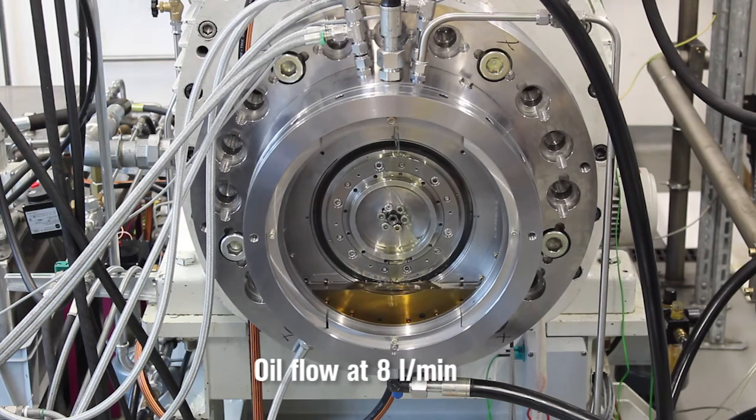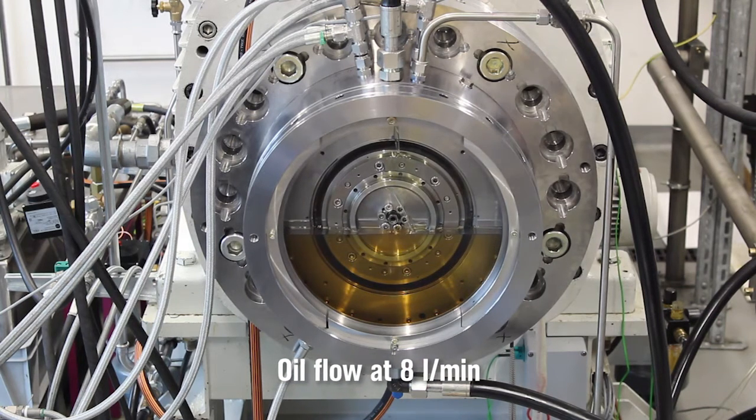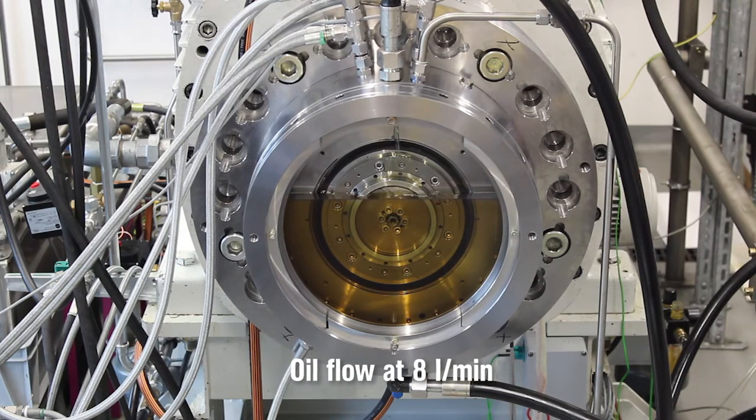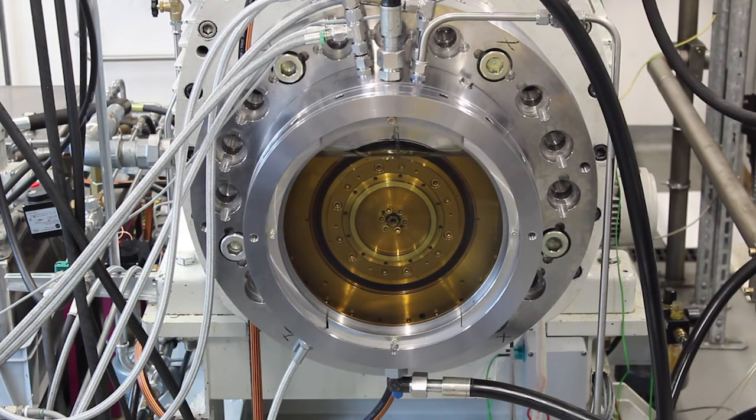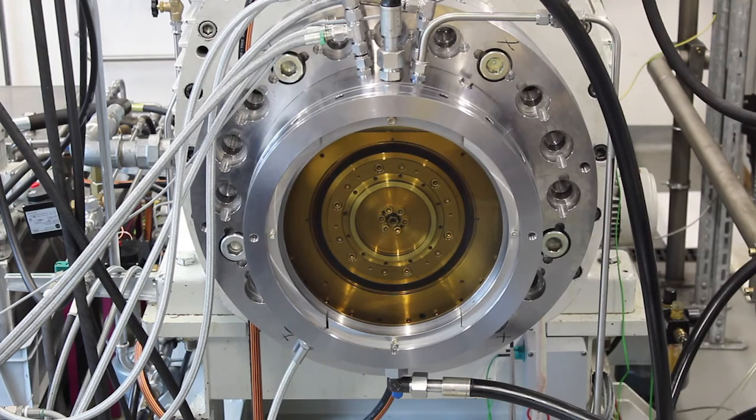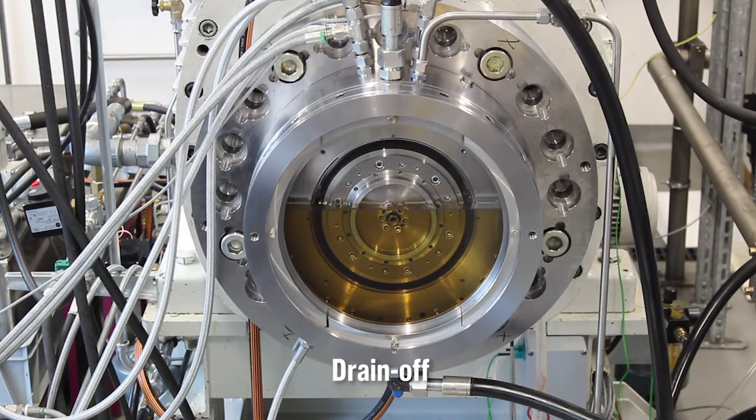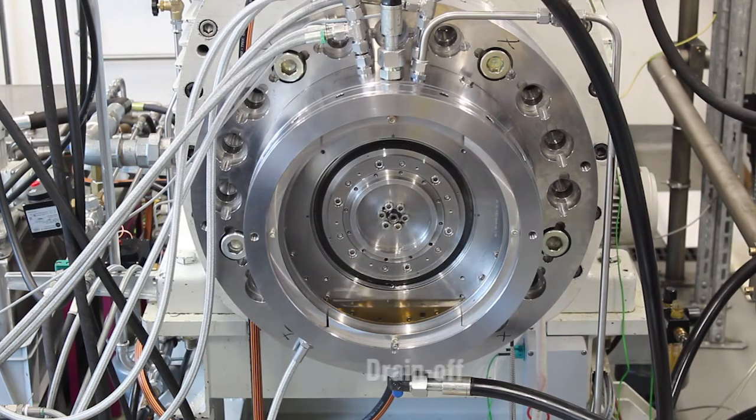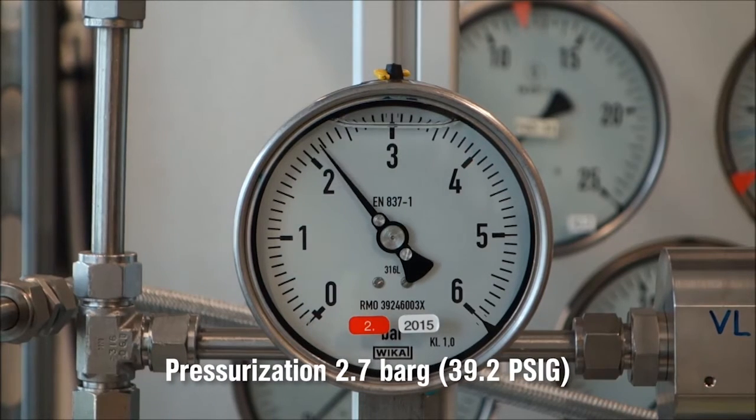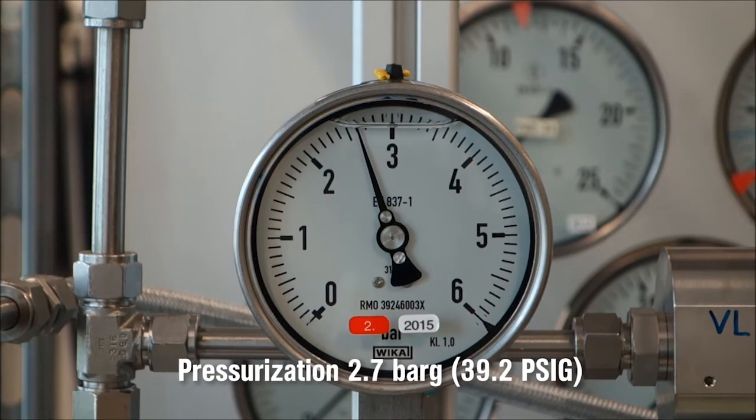Oil is again supplied to the bearing housing at a rate of 8 liters per minute. The difference being that, this time, the housing is completely filled with oil. After five minutes, the oil is then drained off again, and the pressure is increased once more to 2.7 bar gauge.